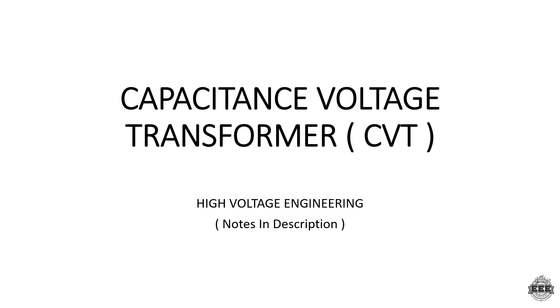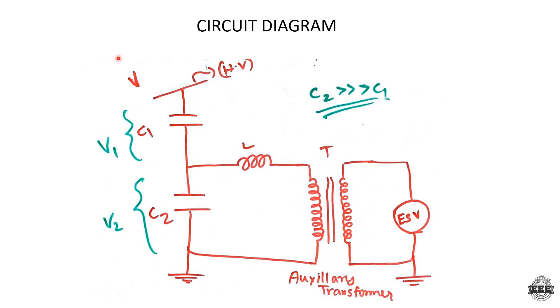Capacitance Voltage Transformers is an interesting case. The CVT circuit diagram has three major components. The first major component is the potential divider, consisting of C1 and C2. High voltage V1 and V2 are divided by this potential divider. The second part is the resonance circuit. The third component is the measuring device - an ESV, electrostatic voltmeter - connected to the output for voltage measurement.